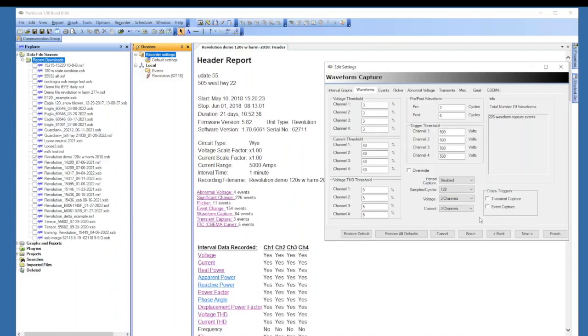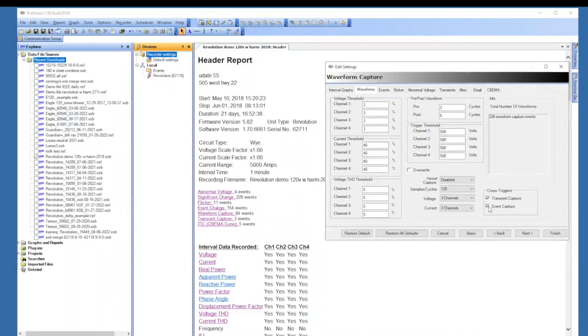And then the Revolution does cross triggers. There's a transient option in the Revolution. So with that checked, that means that if it does take a transient, then it will take a waveform capture that includes the transient. A transient waveform capture looks about a third of a cycle, a picture of about a third of a cycle. And then event capture, I usually don't set that. That has to do with the next tab there. And I think it does double duty, and sometimes if you don't set the event capture right, you'll get a lot of waveform captures.